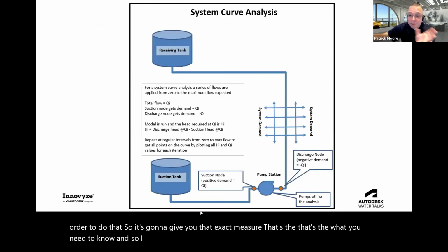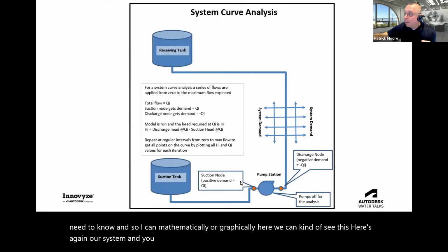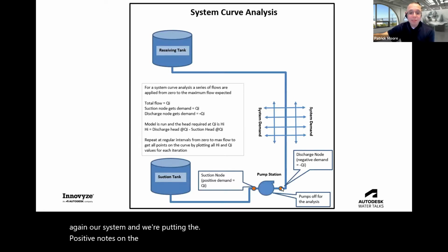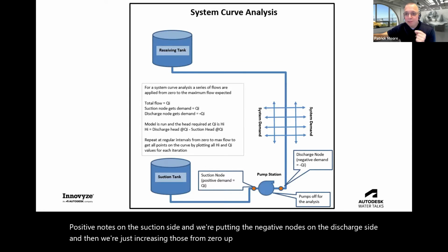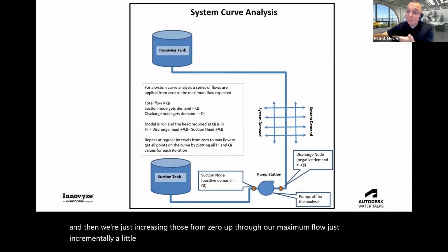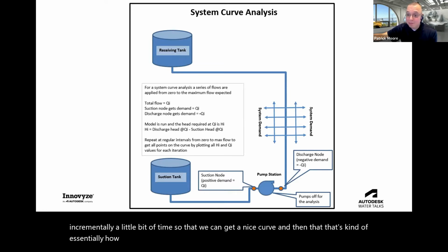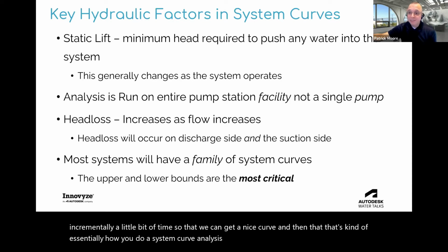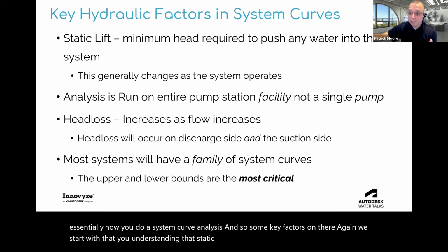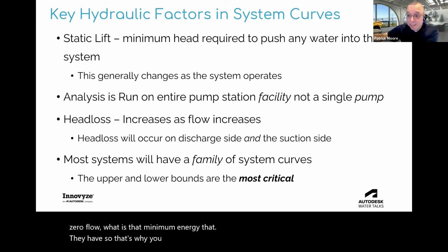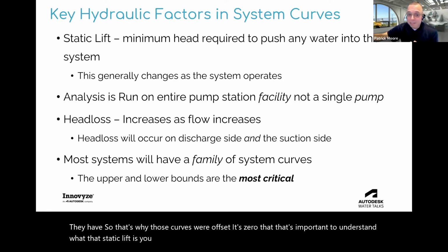And so mathematically or graphically, we can kind of see this. Here's, again, our system, and we're putting the positive demand on the suction side, and we're putting the negative demands on the discharge side. And then we're just increasing those from 0 up through our maximum flow, incrementally, a little bit at a time, so that we can get a nice curve. And that's essentially how you do a system curve analysis. Some key factors: again, we start with understanding that static lift, that minimum energy. Before I started, at 0 flow, what is that minimum energy that I have? That's why those curves were offset at 0. It's important to understand what that static lift is. Again, we talked about this already, that the analysis is on the station. It's not a pump analysis.